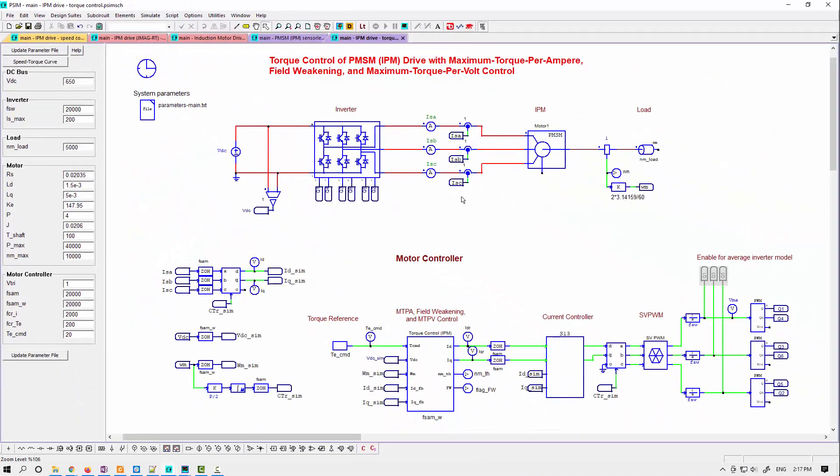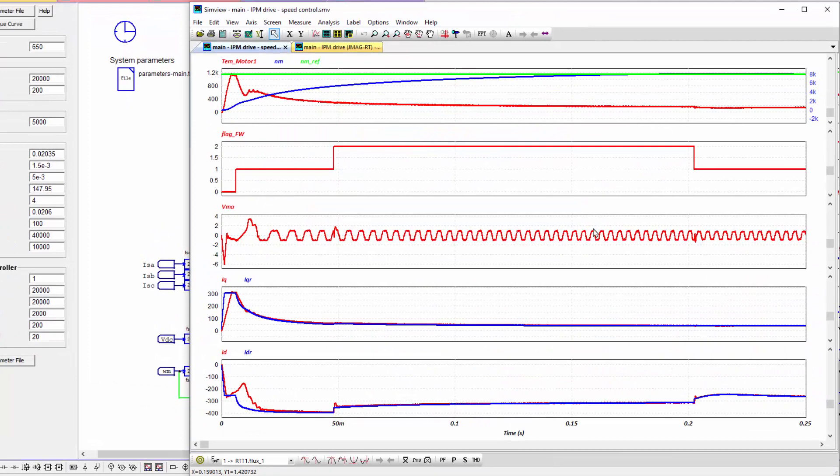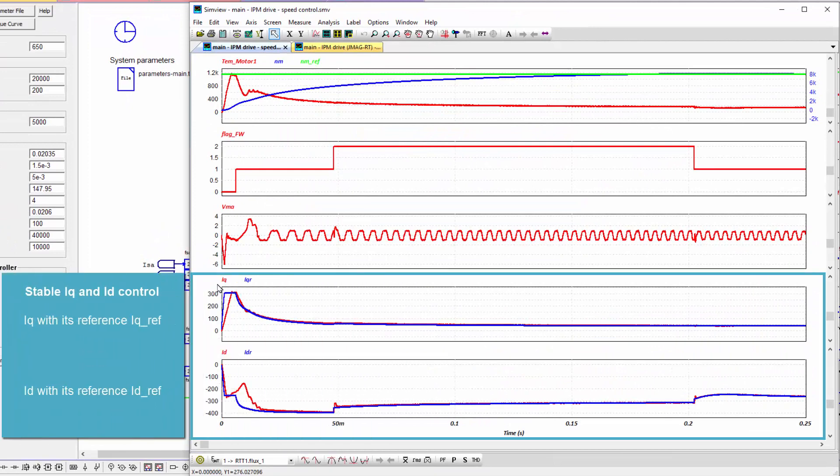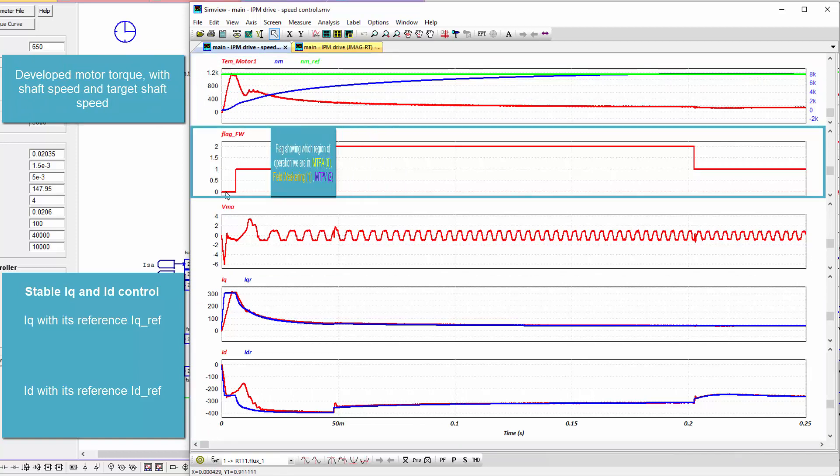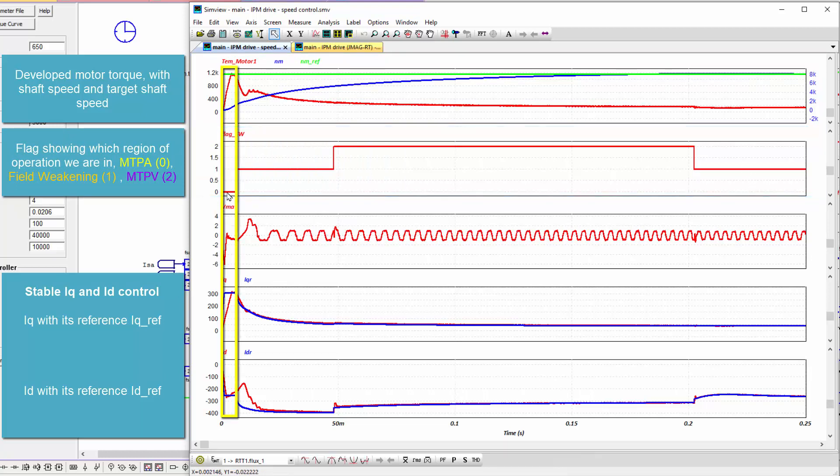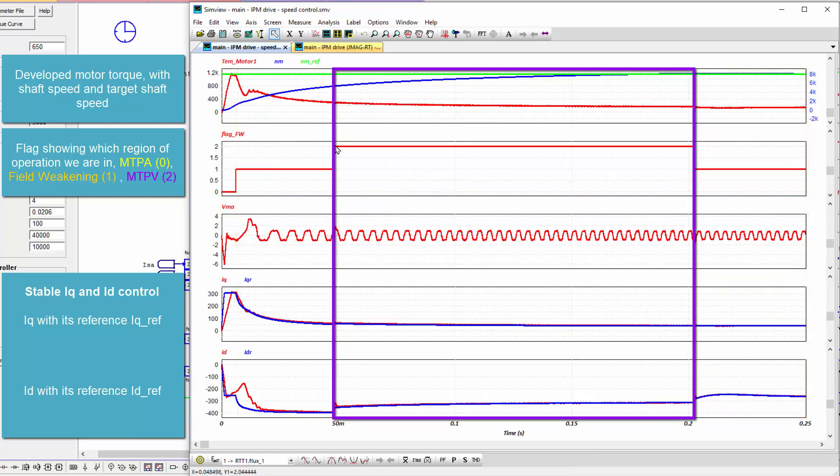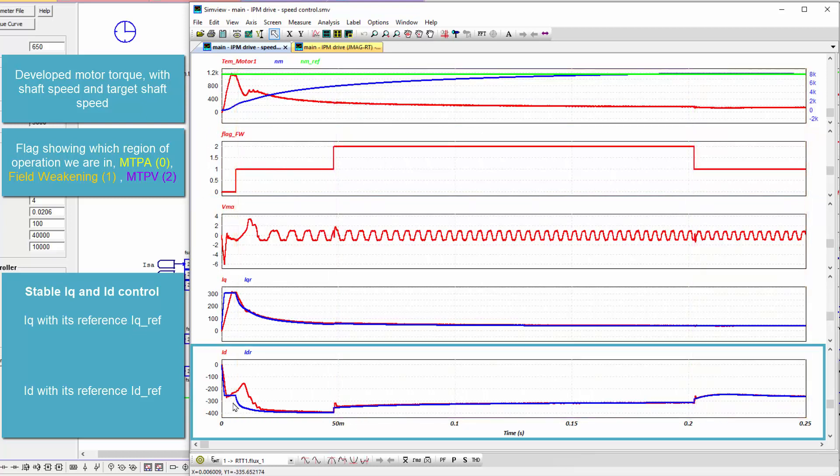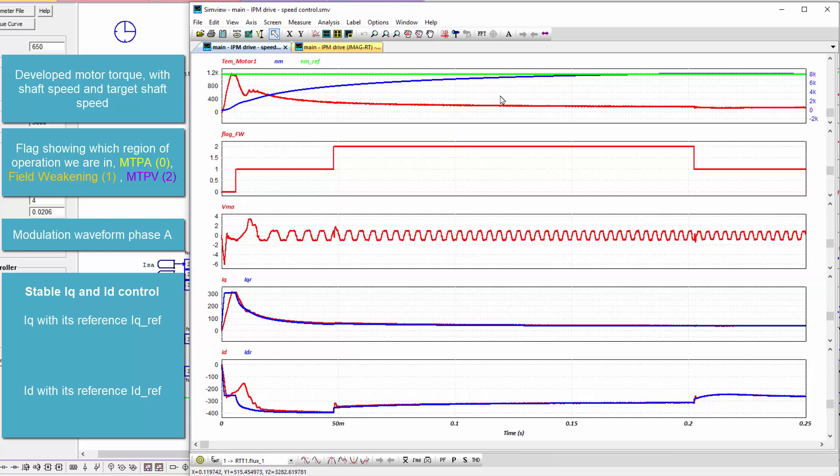When you run the simulation, you'll see some simulation results here. We see stable IQ control, stable ID control, and this is in speed control where we're ramping up towards set point speed here of 8,000 RPM. We can see this flag is indicating when we're in max torque per ampere control region or if we're in field weakening or if we are in max torque per volt control. We can see how ID changes in each of those different regions as we work to maintain maximum torque and operating conditions out of this machine as we hit set point speed.